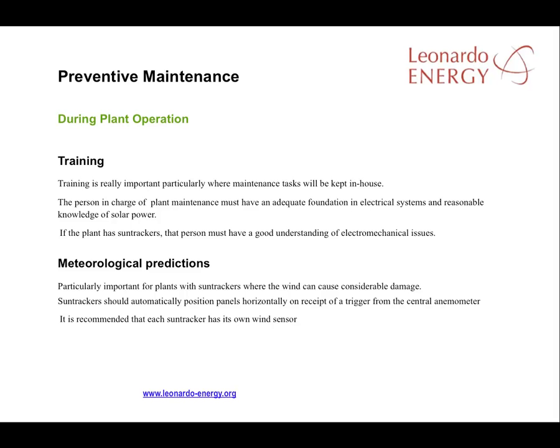Accurate meteorological measures are very important, particularly in plants with sun trackers, where the wind can have a major effect on performance. Many sun tracker systems will place modules in a protective position once they receive a warning signal from a central anemometer. A wind sensor for every sun tracker is the best solution, but that can be an expensive one.